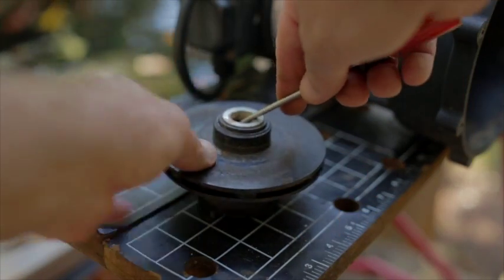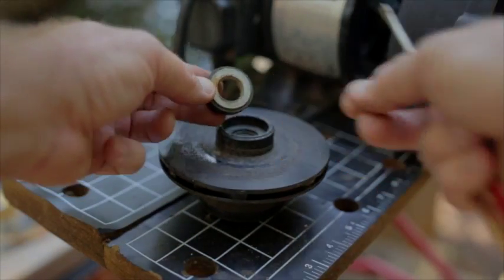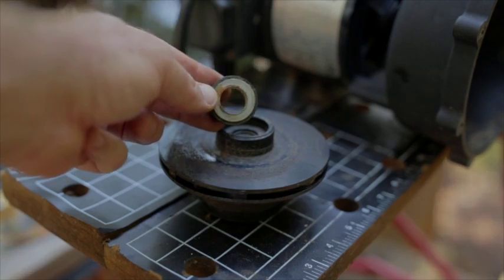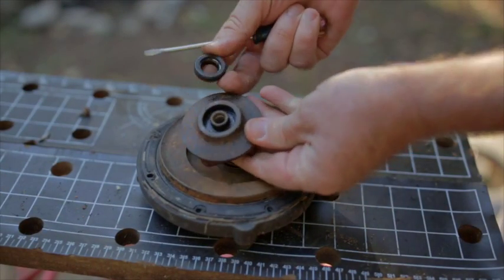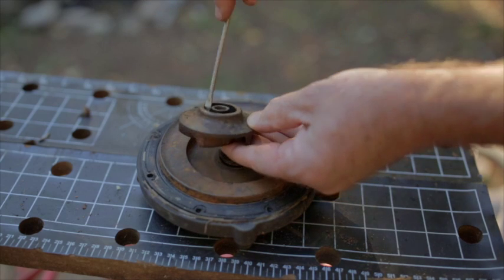When you get the impeller off, you'll see half of the ceramic seal on the back. Carefully pry this out with a small screwdriver. Here is a look at a similar design on a STA-RITE pump. There are several impeller designs out there, and some will be easier to get out than others.